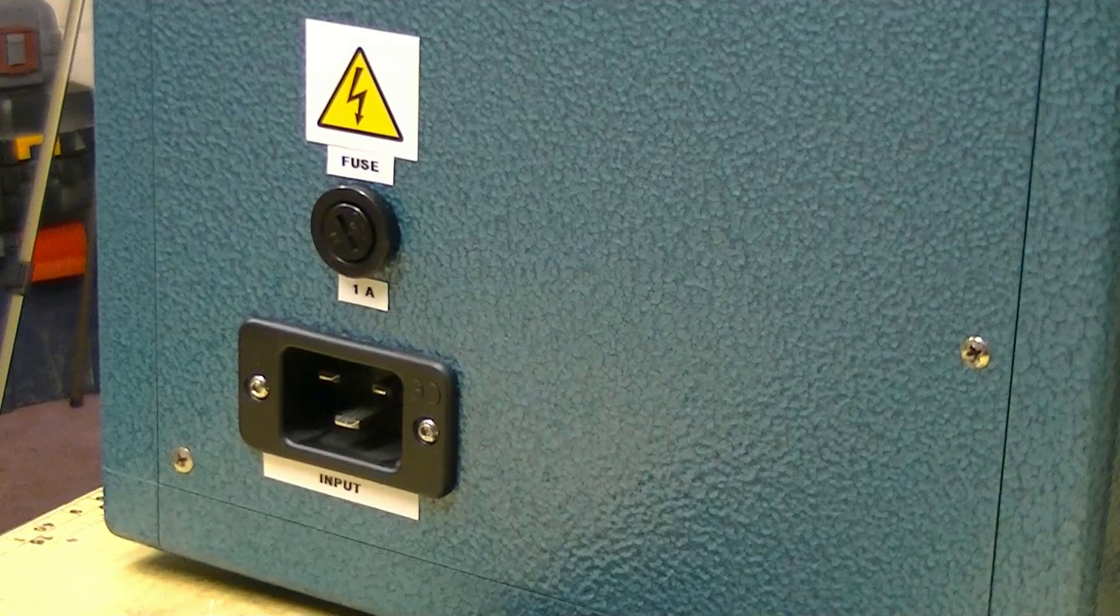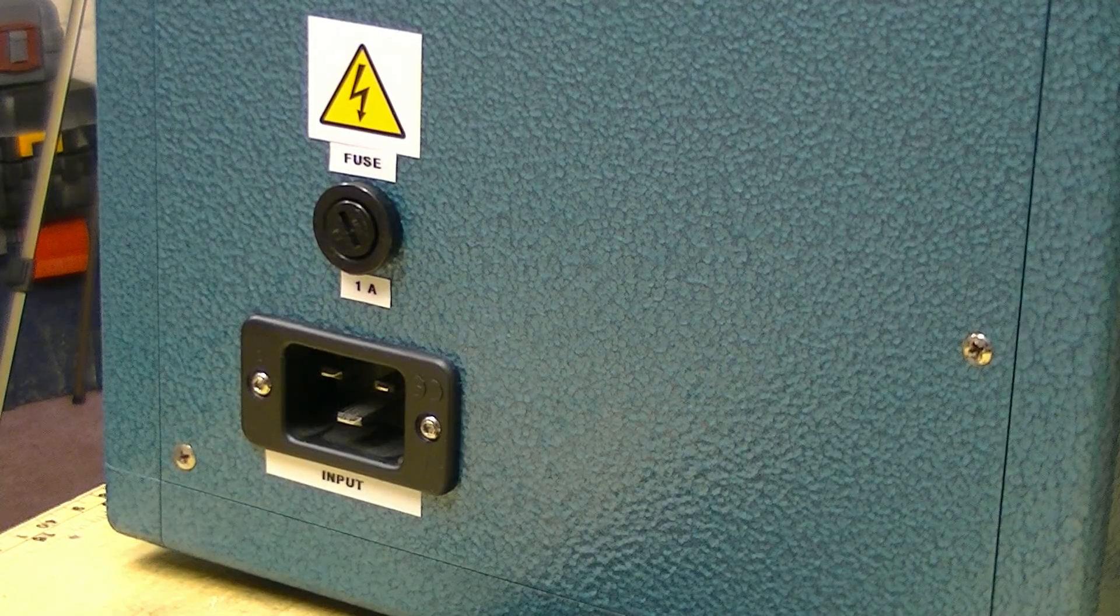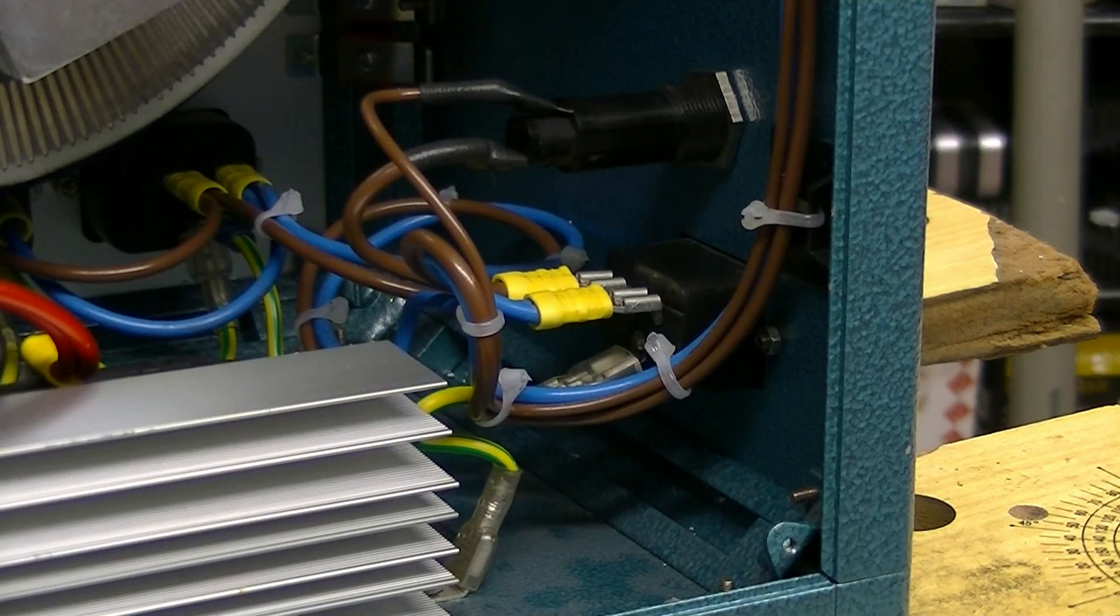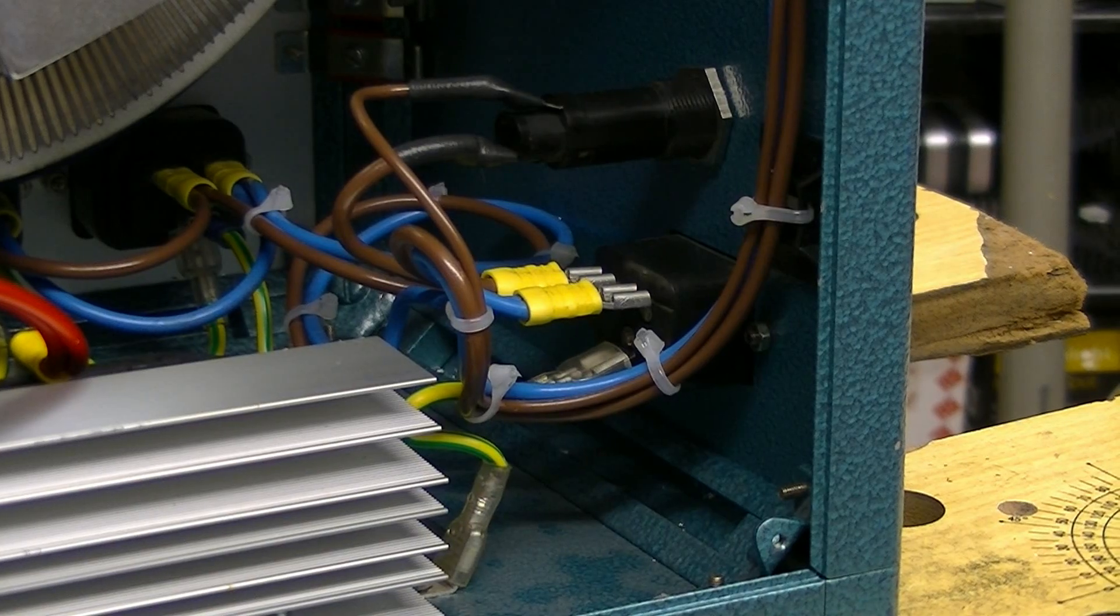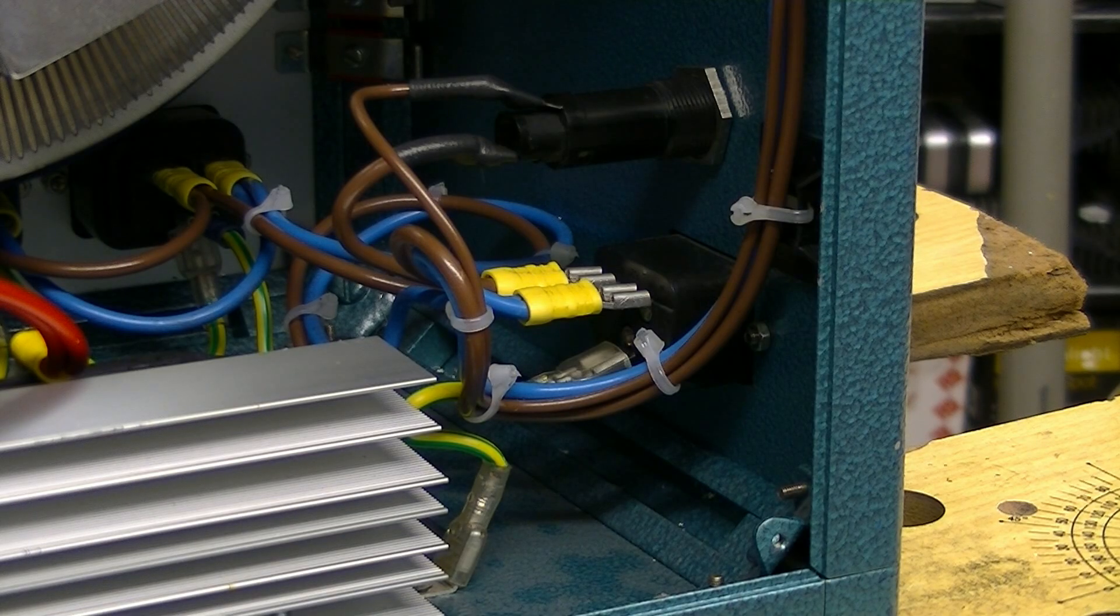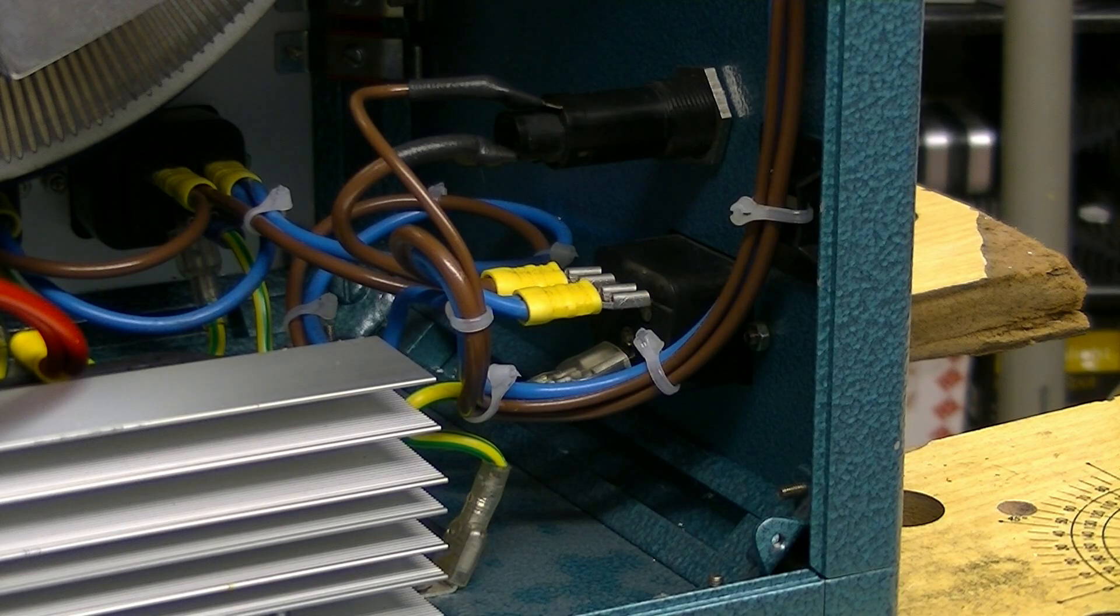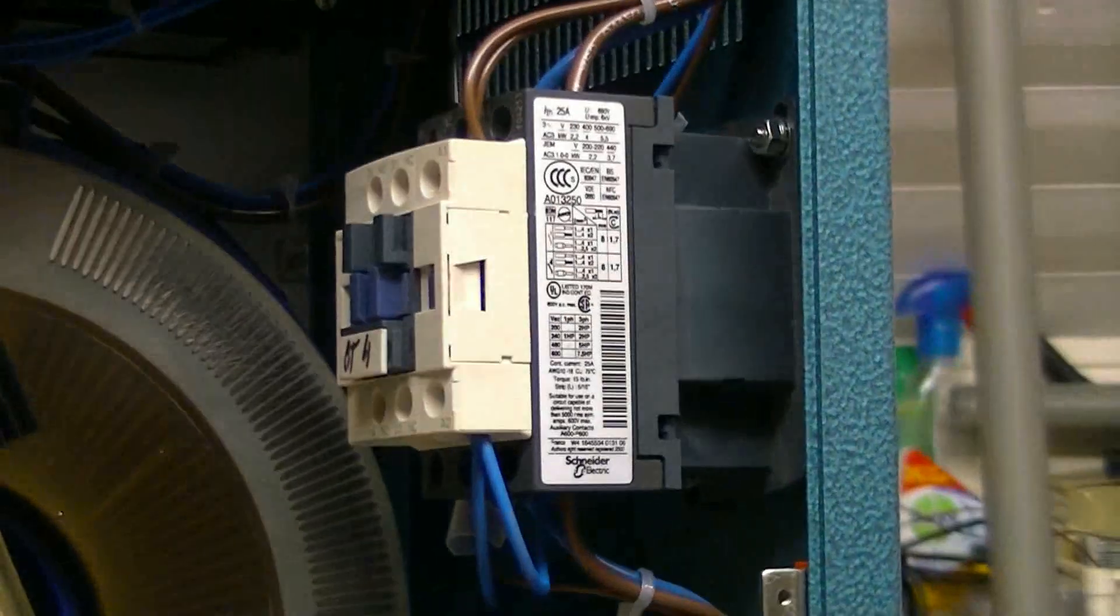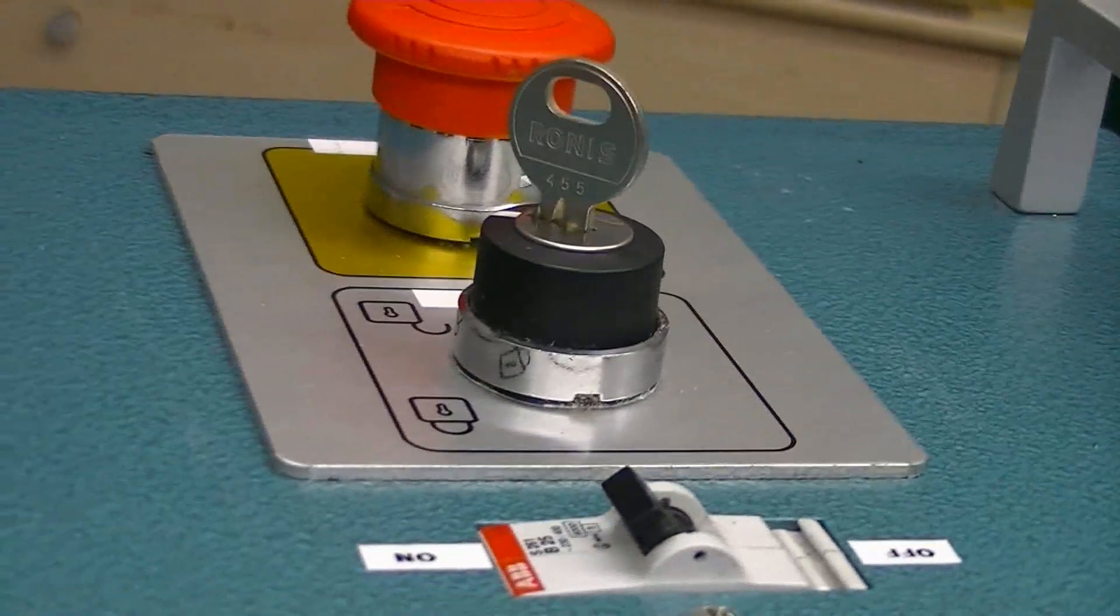There's our mains input, and this time we've got a small 1 amp control fuse. And you'll see why, this one's actually wired up now correctly, as when I first got this it was actually wired up reverse polarity on the mains, which is potentially dangerous on a variac. Zero volts, you don't want that there's 240. So there's our input and it goes up to the control fuse which now controls that contactor via stop button and that key switch.